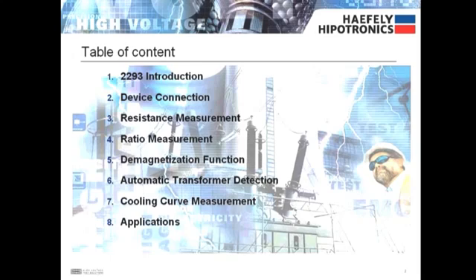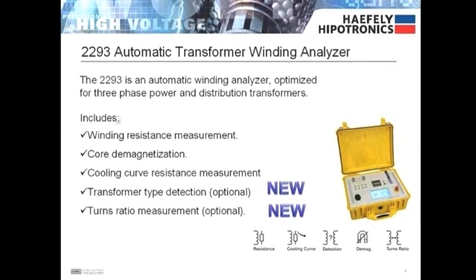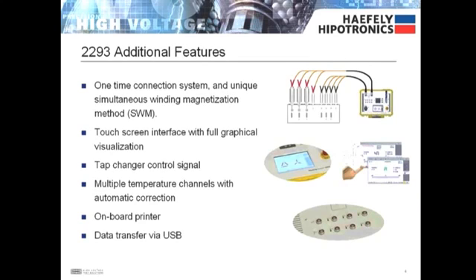The 2293 is an automatic winding analyzer optimized for three-phase power and distribution transformers. It includes winding resistance measurement, core demagnetization, cooling curve resistance measurement, and the newly released optional turns ratio measurement and transformer type detection. Additional features include a one-time connection system, simultaneous winding magnetization method, touchscreen interface, tap changer control signal, multiple temperature channels, onboard printer, and data transfer via USB.